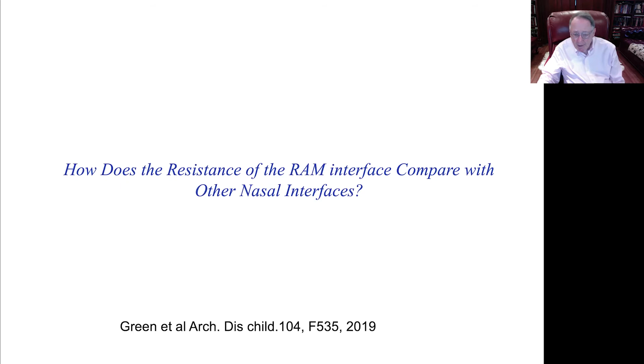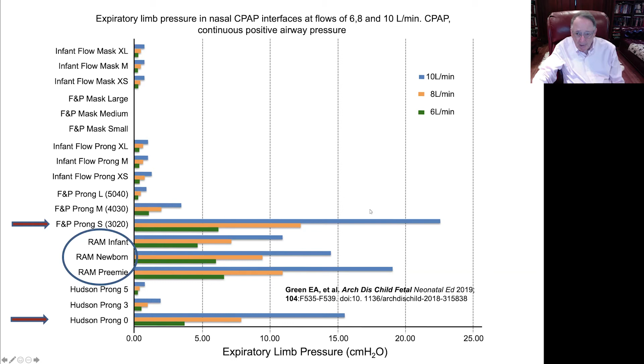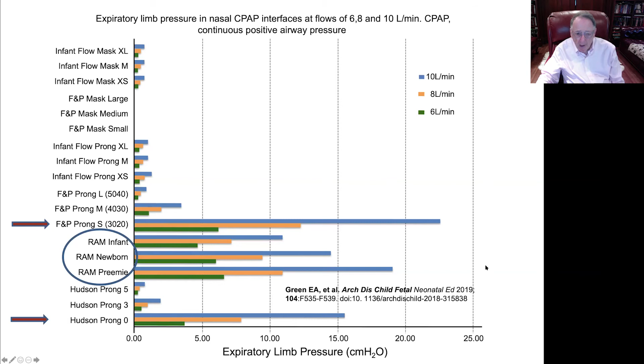How does the resistance of the RAM cannula compare to other devices? This is an in vitro study which looked at all the devices, masks and various commercial devices like Fisher Paykel and Hudson prongs. You can see that all sizes of RAM cannulas have a pretty high resistance, and the longer the bar, the higher the resistance. They looked at 3 different flow rates: 6, 8, and 10 liters per minute. But the smallest Hudson prongs, to be fair, and the smallest Fisher Paykel prongs also have a fairly high resistance.